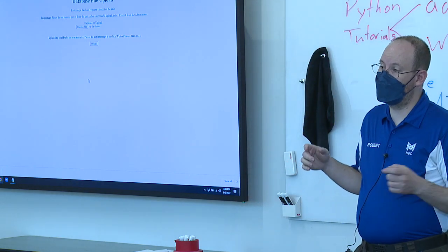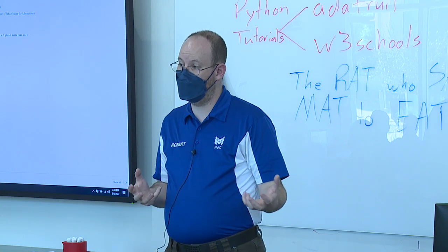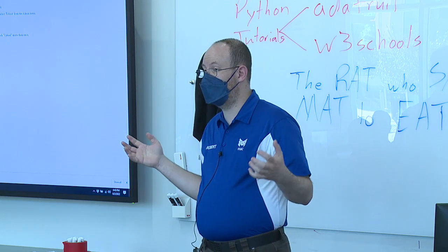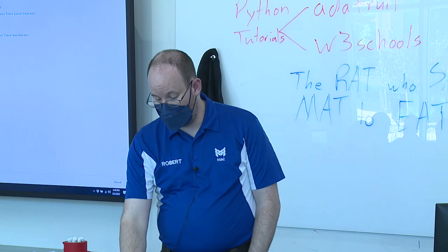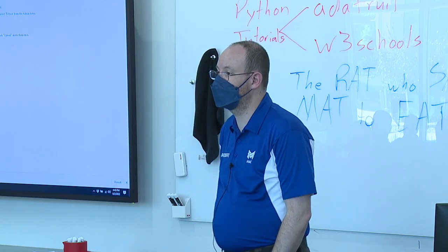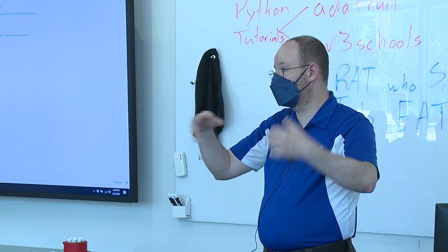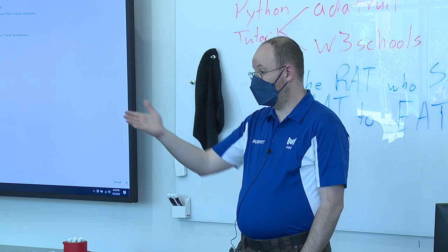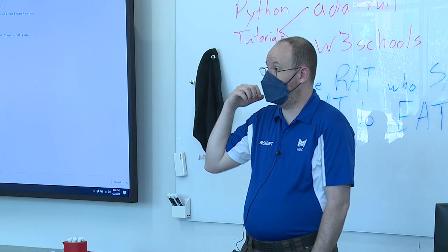Okay? I will caution you about one thing with the blank database file. Because of how you have to create a blank database file initially, there will be a username and password set on the controller. So the first thing, when your new students show up, maybe you do this before they walk in the door, you're going to have to do the little reset trick again to get it back to the factory default password. Or if you want to start them off with an existing account, with your hello CC1 or whatever password you want to give them, when you log in on a brand new unit, just automatically grab that database. And then you'll have your own custom blank database.